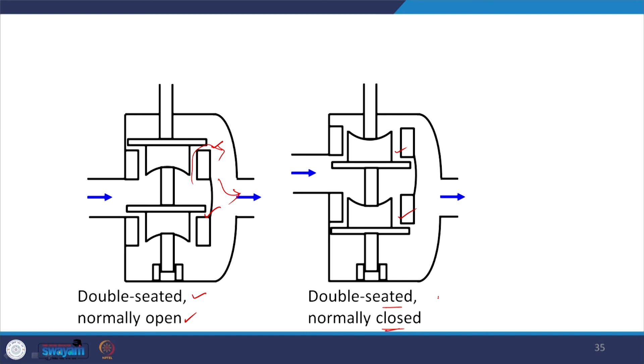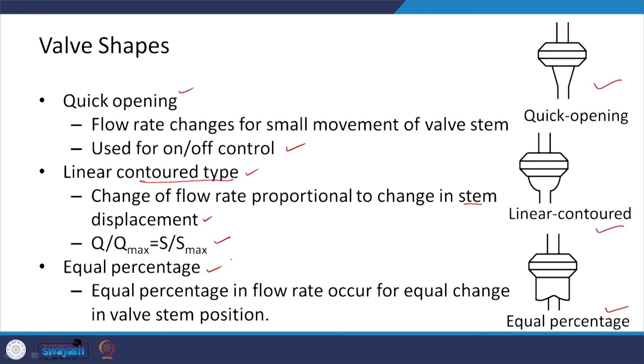There are various shapes of the valve: quick opening, linear contoured and equal percentage. Okay. The quick opening valve changes flow rate for small movement of the valve stem, as the name indicates, they are quick opening and these are used for on off control. Then the linear contour type, the change of flow rate is proportional to change in stem displacement. Okay. So, you have the Q by Q max is equal to S by S max relationship applicable in the linear contour type, where S is the stem displacement and Q is the flow rate, and the equal percentage type gives an equal percentage of flow rate change for equal change in the valve stem position.